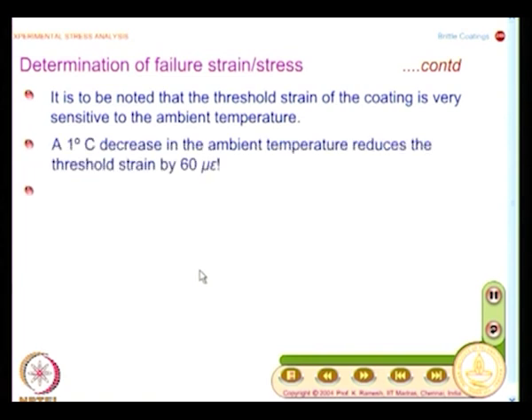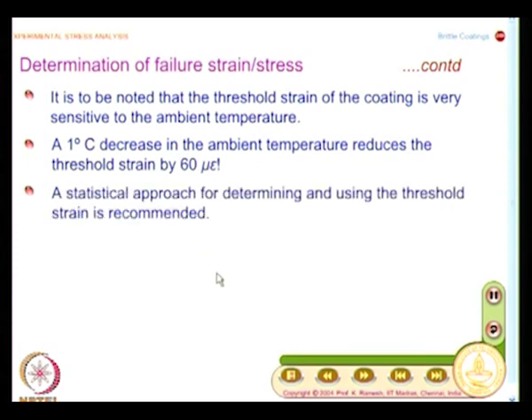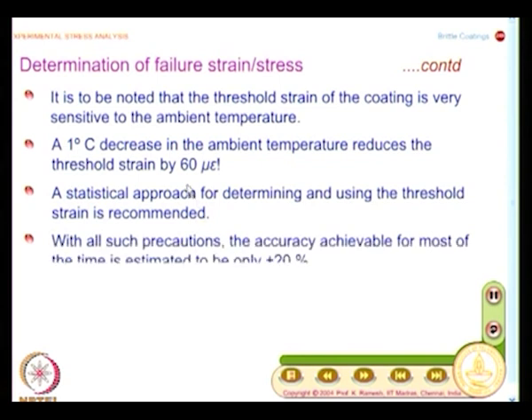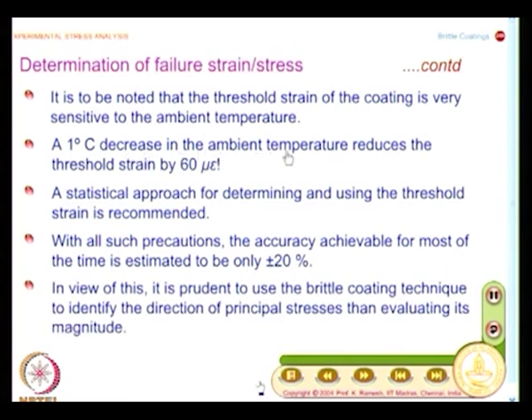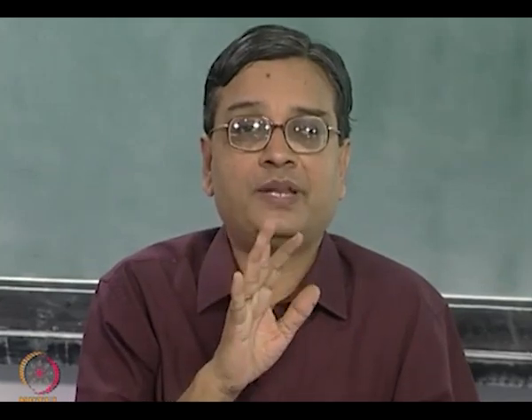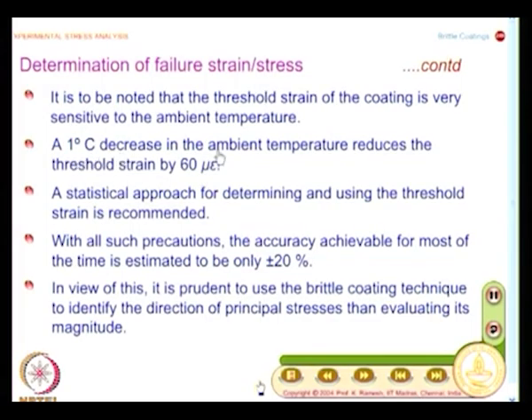And you must also keep in mind that the environment plays a very important role. What is reported is that even a 1 degree centigrade decrease in the ambient temperature reduces the threshold strain by 60 microstrain. It is very large. See, what you need to keep in mind is that when the temperature is lowered, the coating behaves more brittle. So, you have to be very careful about temperature and the relative humidity; these are very important. You must maintain that, and you must also look at the chart supplied by the manufacturer to check that you have used the appropriate coating for a given application, and also ensure that you follow the recommendations.